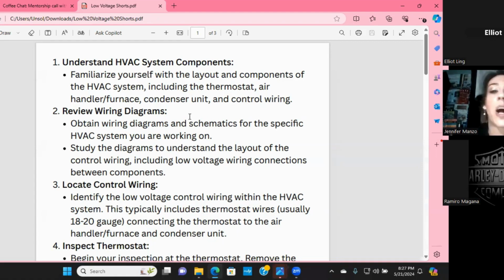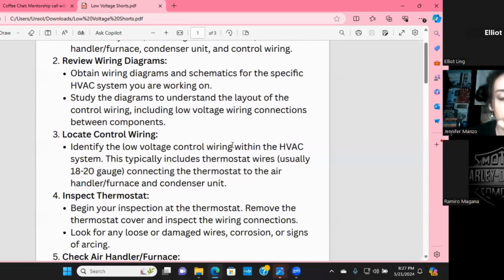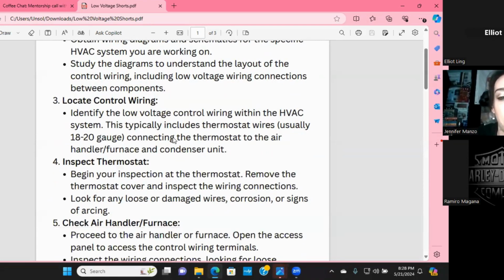So familiarize yourself with not only the field wiring part, which is obviously your common 24 volt, but also with the factory wiring. That's important. And then locate your control wiring. As we know, sometimes the control wires come into the unit in a weird place, not where it's supposed to come in, or it comes in the right place and it looks very different because whoever installed it was a cheapo and didn't want to buy the right two or four wire. So always make sure that you're locating the correct wiring before you start to troubleshoot it.